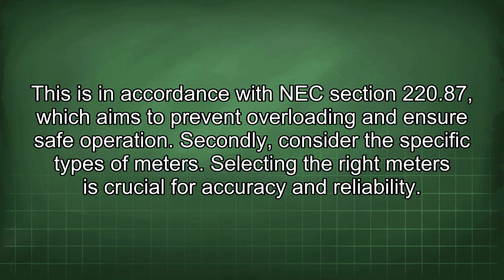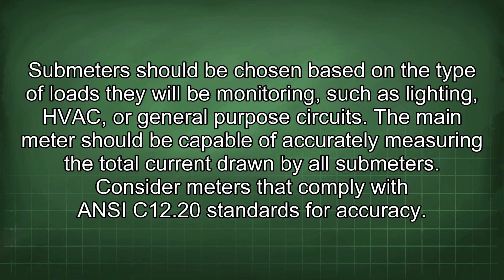Secondly, consider the specific types of meters. Selecting the right meters is crucial for accuracy and reliability. Submeters should be chosen based on the type of loads they will be monitoring, such as lighting, HVAC, or general-purpose circuits. The main meter should be capable of accurately measuring the total current drawn by all submeters. Consider meters that comply with ANSI C12.20 standards for accuracy.